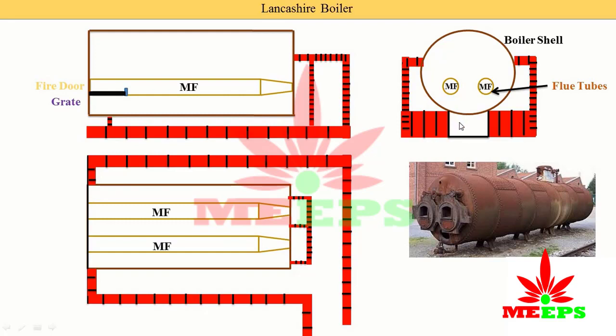The main flow of hot gases from the grate passes through the fire tubes to the back end. After this it goes to the bottom flow — meaning the gases exhaust on this side and begin moving along the bottom of the boiler shell, between the shell and the brick. After the bottom flow, the gases move to the front of the boiler and then into the side flow (SF). In the top view, this is referred to as side flow because the bottom is only visible from the side and front views.